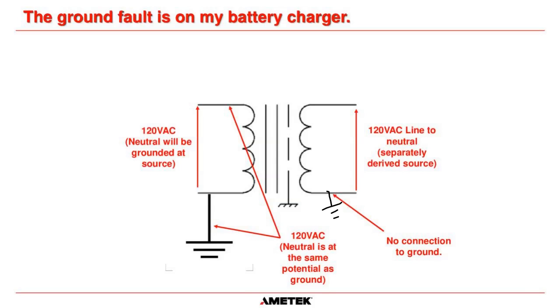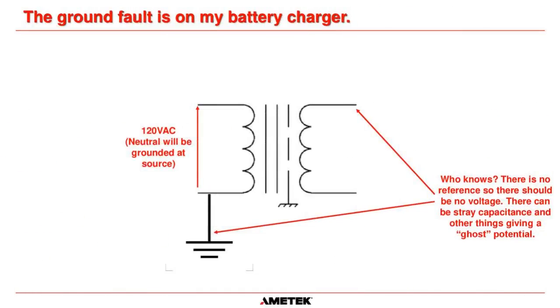Okay? And follow me, there's a reason why I'm going through this, so just stay with me. If you measure at this point here, hot to ground with a Fluke, you're going to get 120 volts AC. But on this secondary side, if you measure from this point to ground, there is no reference anymore. What is the voltage going to be? Well, who knows? There is no reference, so there should be no voltage, actually. There should be no potential difference.